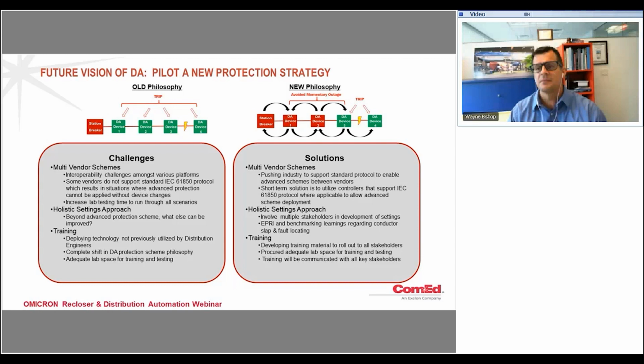And so now below are some challenges and solutions that we came across for our new philosophy here. So one of the challenges we have seen is our multi-vendor schemes. They result in interoperability challenges amongst various platforms. And then there's some vendors that just do not support the standard IEC 61850 protocol, which results in situations where advanced protection cannot be applied without actually changing out devices. And also we'll need to increase the lab testing time to run through all these different scenarios.